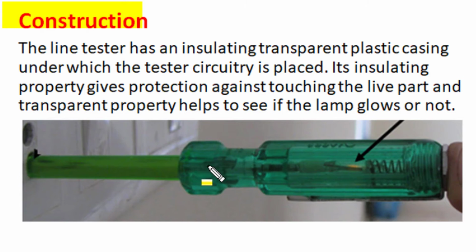It has an insulating transparent hollow plastic casing under which the tester circuitry, spring contact, neon lamp, high resistance and metal rod connections exist. The insulating property of this plastic casing provides protection against touching the live part of the test circuit, and its transparency helps us to detect the glow of the lamp, whether it is there or not.